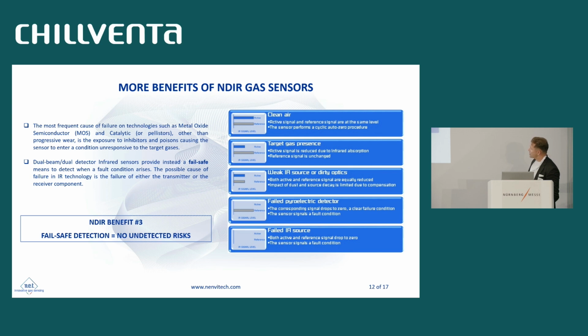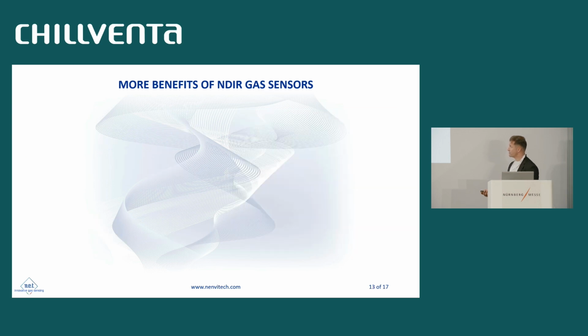When the IR source decays over time, or there is a deposit of contaminants on the optics, both signals are attenuated, and therefore we can apply compensation. If one of the pyroelectric detectors fails, the corresponding signal drops to zero, and that is a clear fault condition, which is signaled by the sensor. The same applies to a failed IR source: both signals are at zero, and that is also a condition that the sensor is able to report. That is called fail-safe detection, and that means that you have no undetected risk.